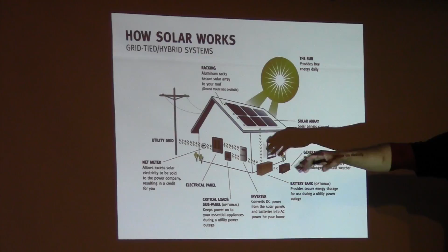Starting with the 2014 National Electric Code, any system that touches the utility grid has to have what's called a rapid shutdown. That means if utility power is lost—because typically what the firefighter will do is just pull the meter out to make the whole house dead—the DC power needs to be disconnected back to within 10 feet of the PV array, so they're not swinging axes and saws and hitting live DC conductors, which could be a real problem. That rapid shutdown requirement's been there since the 2014 code, and most jurisdictions have adopted it now.